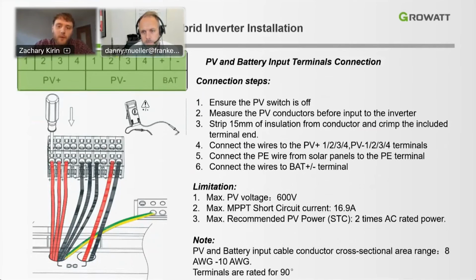Great. Okay. So for the PV and battery input connection, we're going to follow steps 1 through 4 or 1 through 6 here in this particular slide. So the battery and PV input terminals are shown here. We want to ensure that the PV switch is in the off position before we plug the PV array to the inverter. And then before we actually install these, we'll strip about 15mm of insulation from the conductor. And if possible, we can crimp the included terminal ends to those conductors as well.